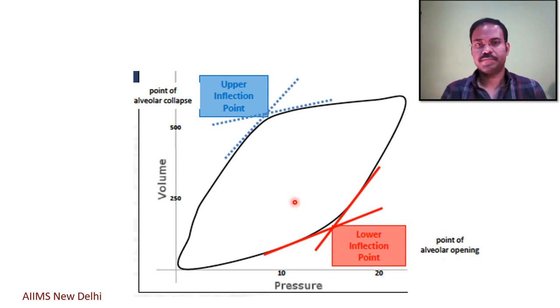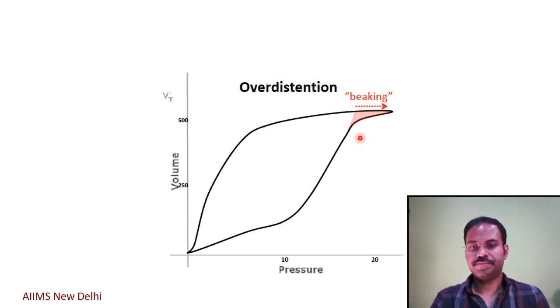Now sometimes you can see this kind of picture, which is called beaking in the PV loop. The beaking suggests that the alveoli are overdistended. Beyond this point, further increase in the peak airway pressure will not deliver any more tidal volume, and we should immediately reduce the delivered tidal volume or reduce the set peak inspiratory pressure in the ventilation to avoid ventilator induced lung injury.